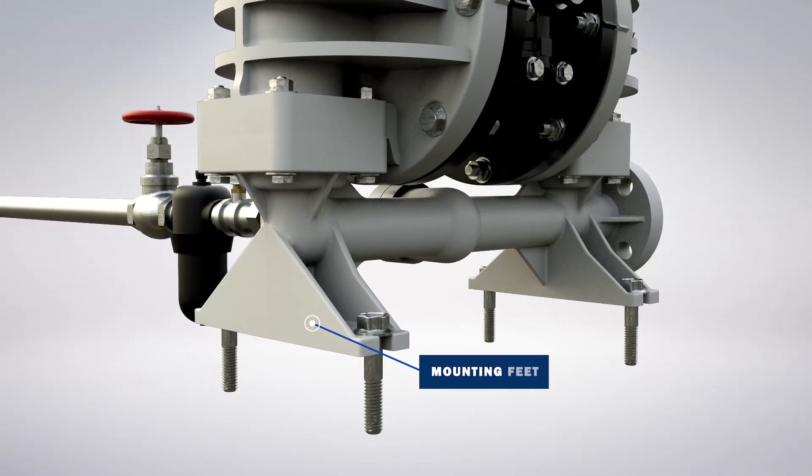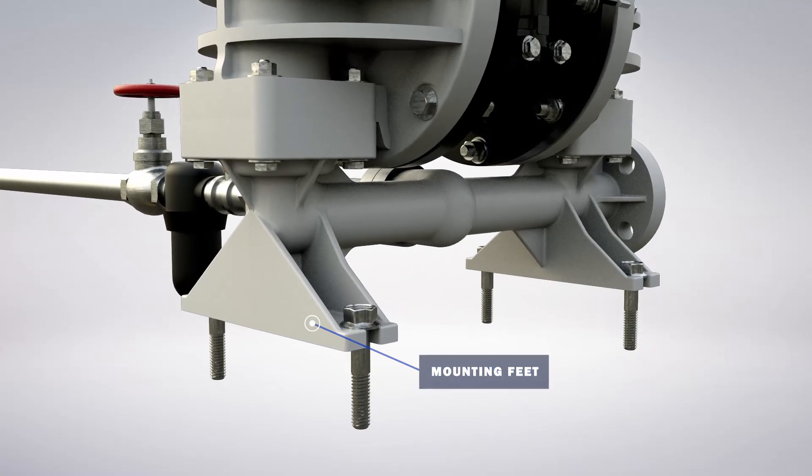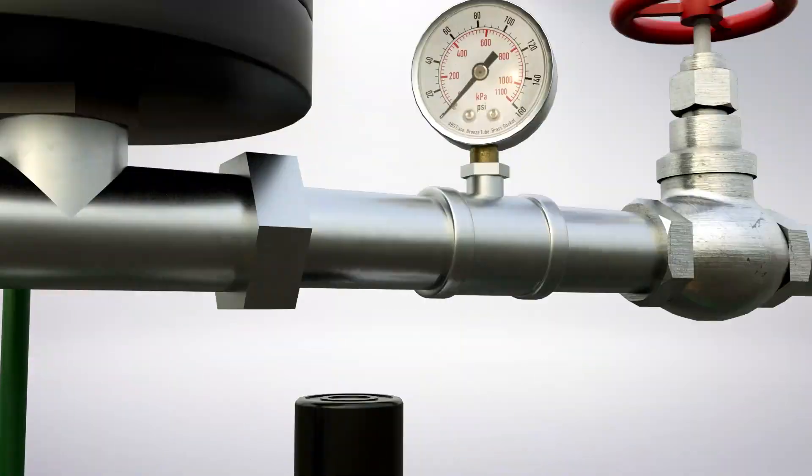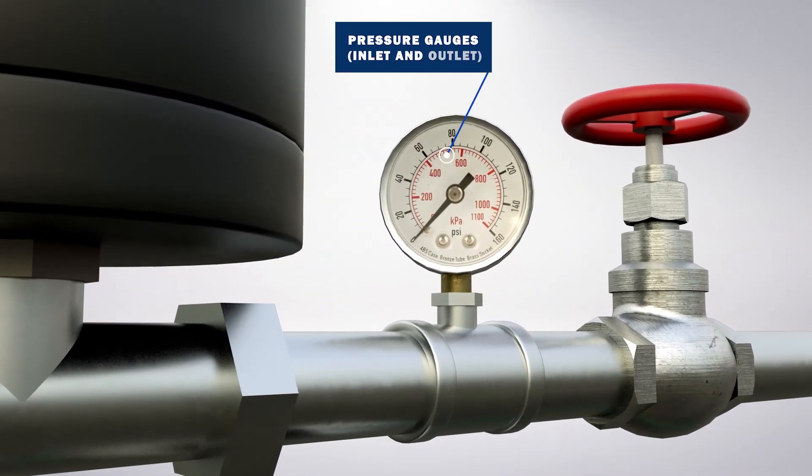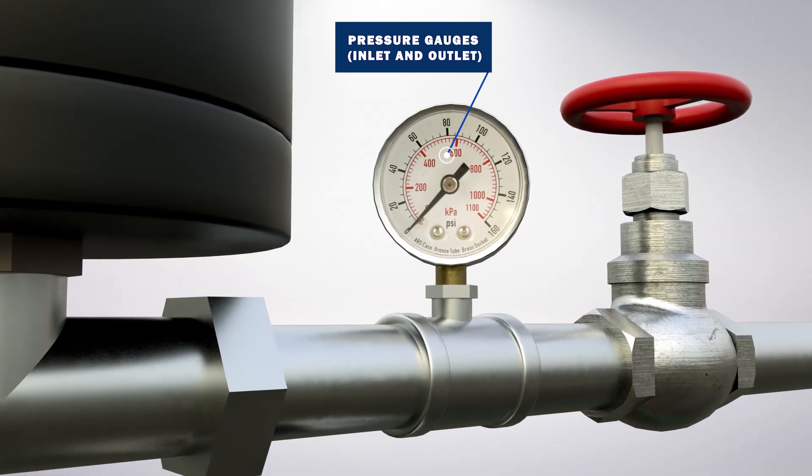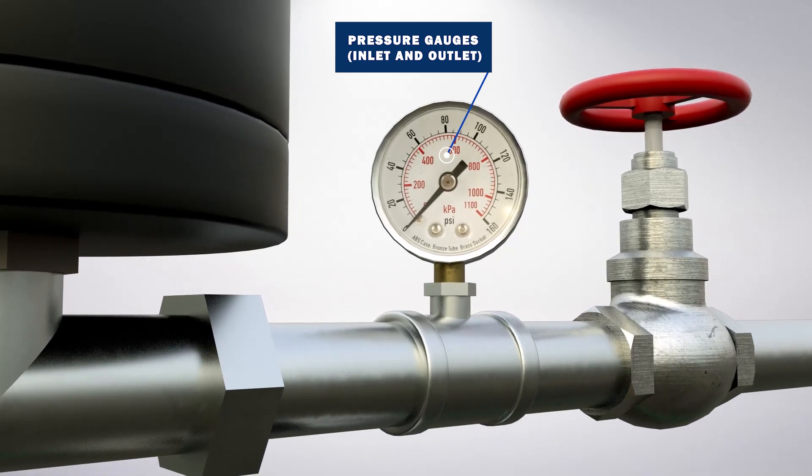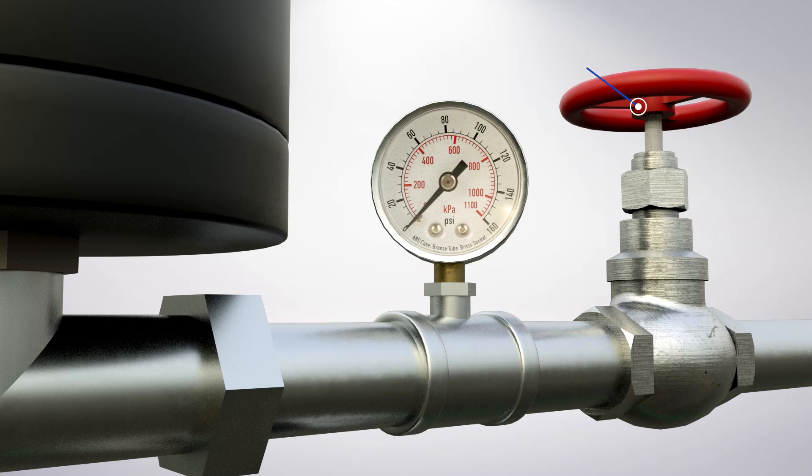The mounting feet can also be used to minimize vibration. Pressure gauges are recommended on both the inlet or suction side of the pump and the discharge side of the pump to confirm pressure. Pressure gauges can assist with any required troubleshooting and can be used to monitor the pump's performance. An isolation valve is recommended to further protect the pressure gauge.